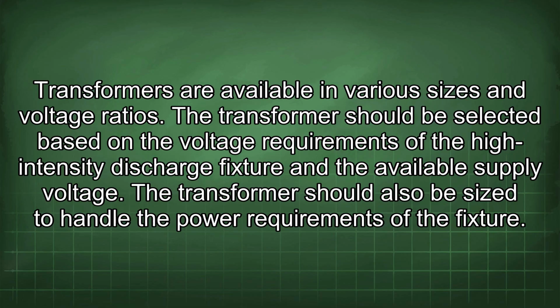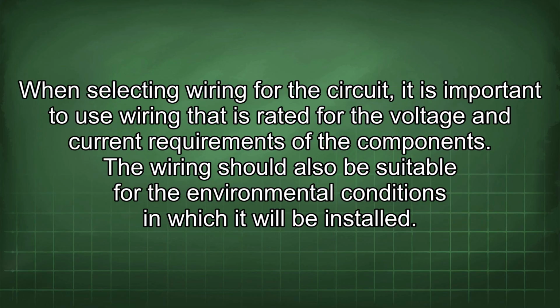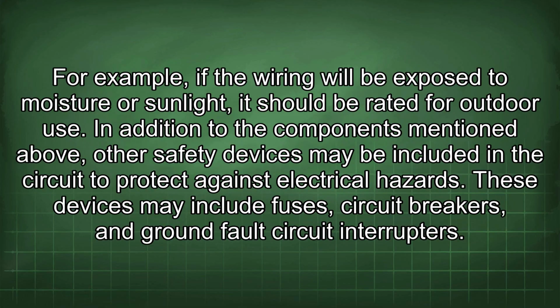Transformers are available in various sizes and voltage ratios. The transformer should be selected based on the voltage requirements of the high-intensity discharge fixture and the available supply voltage. The transformer should also be sized to handle the power requirements of the fixture. When selecting wiring for the circuit, it is important to use wiring that is rated for the voltage and current requirements of the components. The wiring should also be suitable for the environmental conditions in which it will be installed. For example, if the wiring will be exposed to moisture or sunlight, it should be rated for outdoor use.